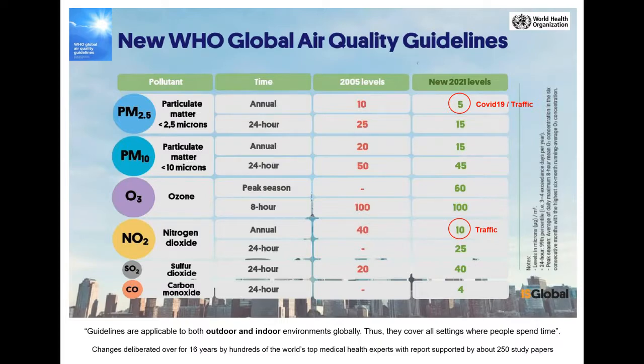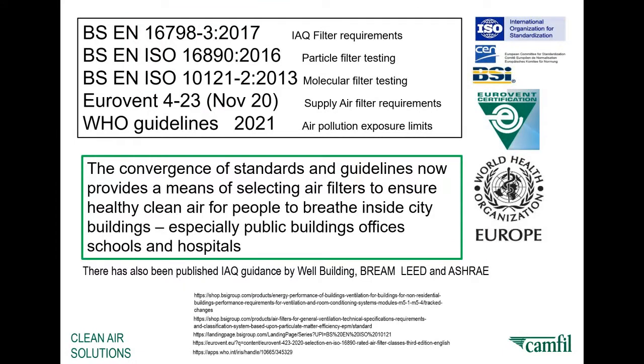Changes have taken place. It's taken 16 years for these to be revised, and they've been deliberated over by hundreds of the world's top medical experts and supported by about 250 study papers. So this isn't something that's lightly been taken on, and it should be taken into account with assessments for what is regarded as clean air or otherwise. There are also supporting technical standards. I think Pawel again mentioned briefly EN 16798. Part 3 is the bit I focus on because it regards categorization of air and uses SUP, ODA and RCA, different types of definitions for air: inside, outside, recirculation. And you also have very good test standards covering particle air filtration and gas filtration, the two types of pollutants you're likely to come across.